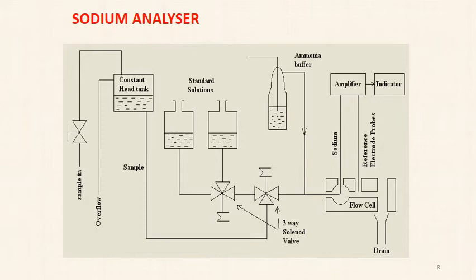Sodium analyzer consists of a constant head tank for storing the sample, the standard solutions for calibrating the instrument, a three-way solenoid valve for allowing either sample or the standard solution, ammonia buffer for pH adjustment, reference and sodium ion specific electrodes for concentration measurement, amplifier and indicator.